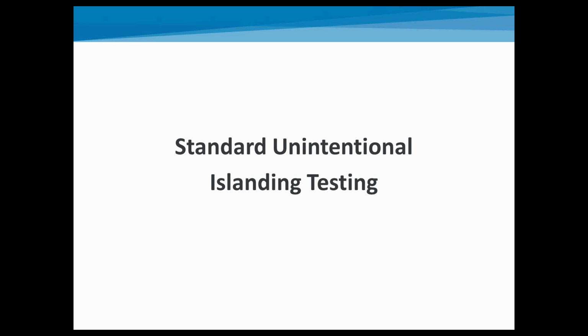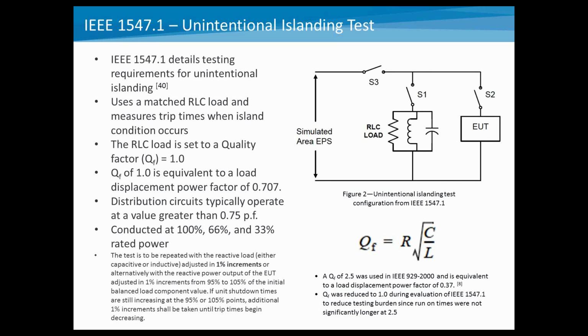Okay, so that kind of talks about the variety of different techniques used to detect and mitigate unintentional islands. I'll talk now a little bit more about standardized testing that's done in this area. Inside of 1547.1, there's an unintentional island test that basically defines how pieces of equipment are tested to evaluate for unintentional islanding capability. The thing to realize about this test is it is only done on a single inverter or a single distributed generator in this case. So in the diagram, you see EUT, that stands for equipment under test, and then that's connected to a load bank.